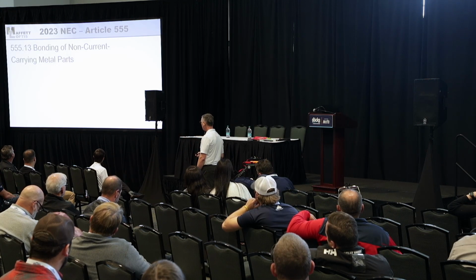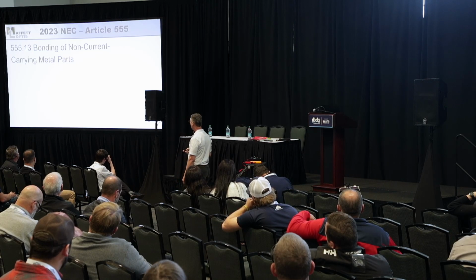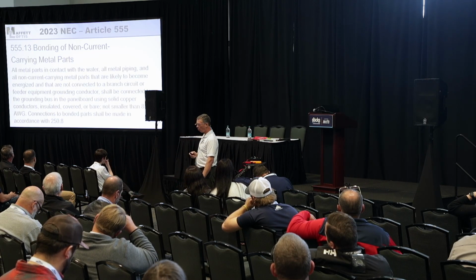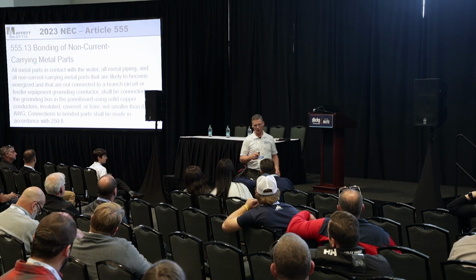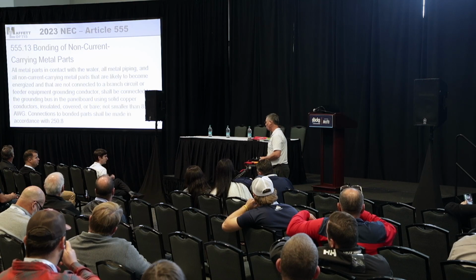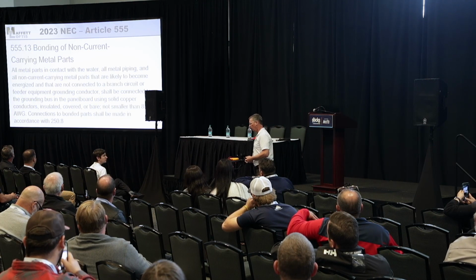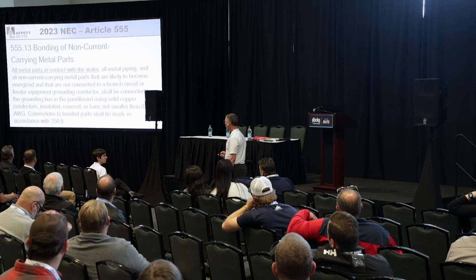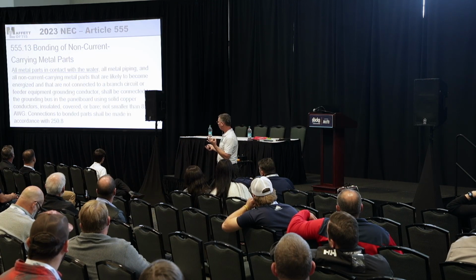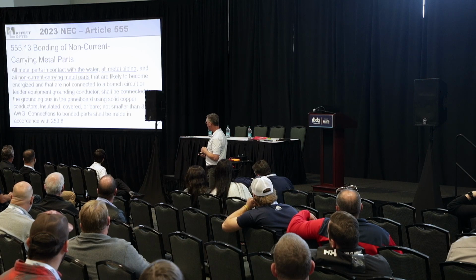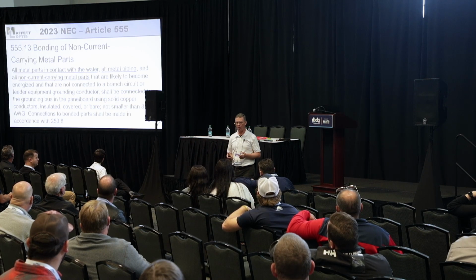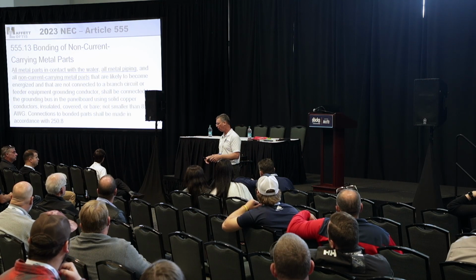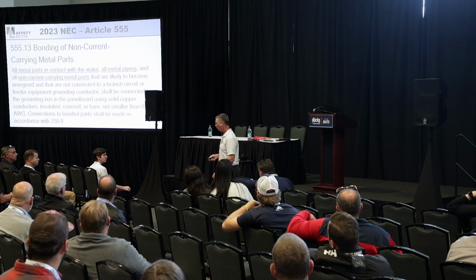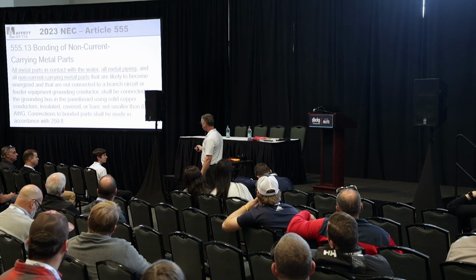But okay, 555.13 is another location where we've changed some code language. This is actually the 2023 text, and I wanted to compare 2023 to 2026, because this is a huge change from what we had in 2023. There's a list of 3 pieces of metal. It says all metal parts in contact with the water, all metal piping, and non-current carrying metal parts. Non-current carrying metal parts could be anything that you could touch. It could be a spud pole, it could be the dock structure itself, maybe some sort of aluminum handrail. But we list those 3 different pieces.